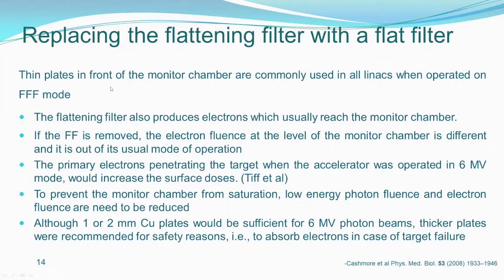A thin plate in front of the monitor chamber is commonly used in all Linacs when operated in triple F mode. And why do you need this flat filter? The flattening filter produced electrons which usually reach the monitor chamber. But if you remove the flattening filter, the electron fluence at the level of the monitor chamber is totally different, and it's out of the usual mode of operation, right? So it is totally different.